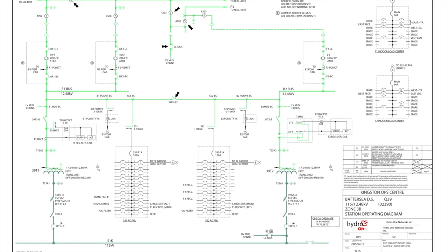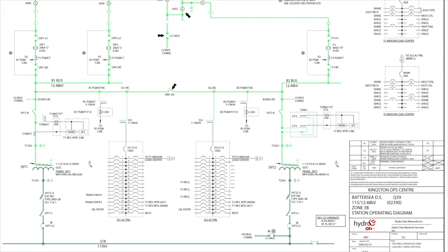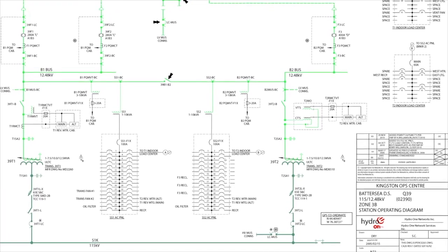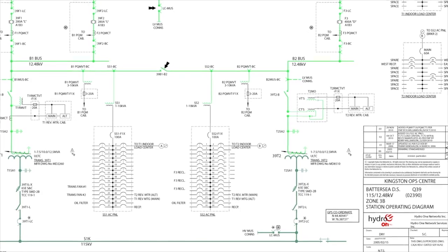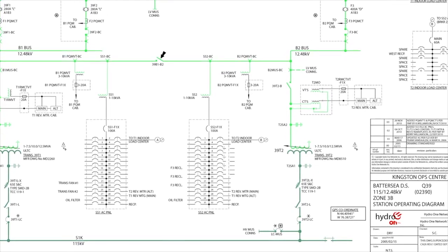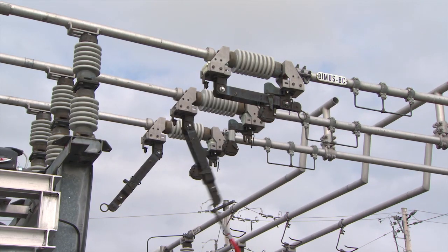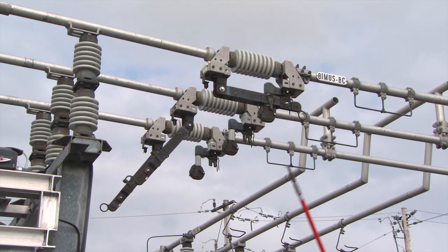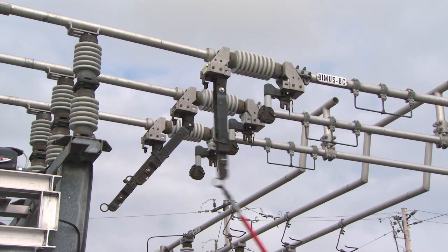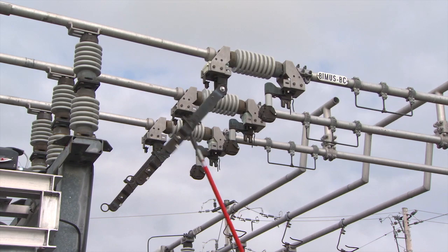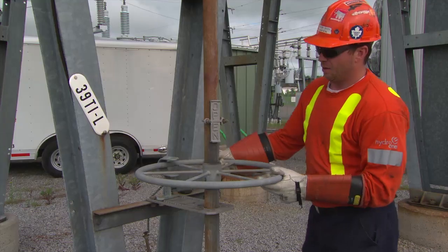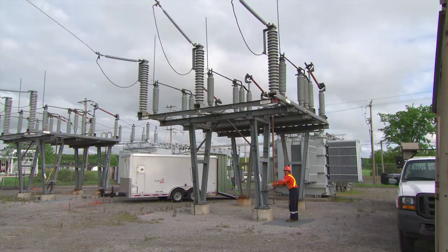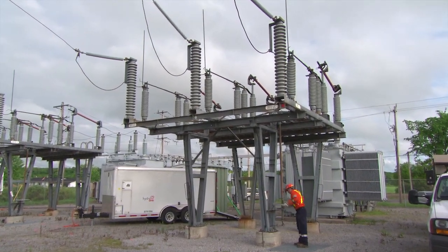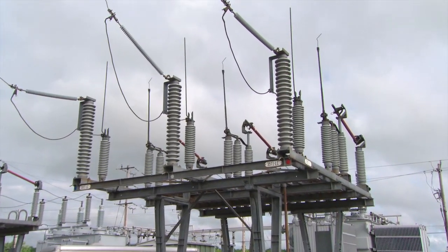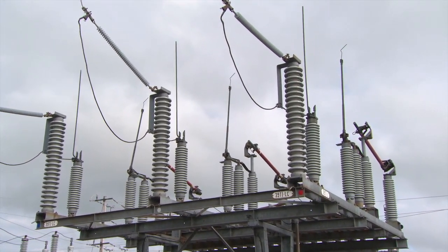At U70 stations, the station reclosers remain in service. The only equipment isolated is the station transformer. Open the DS low voltage switch. The MUS is now carrying the station load. Then open the DS high voltage switch. The station transformer is now off potential.